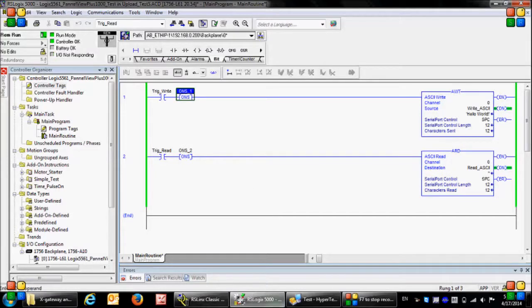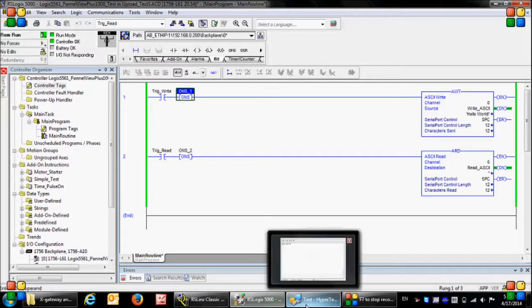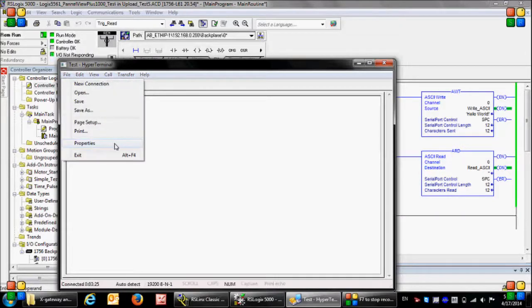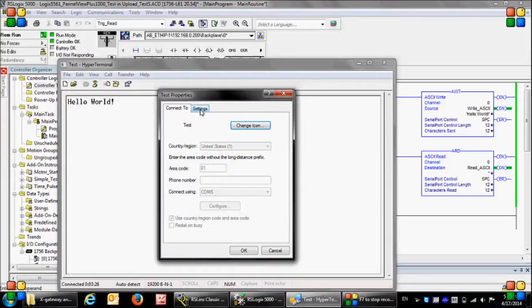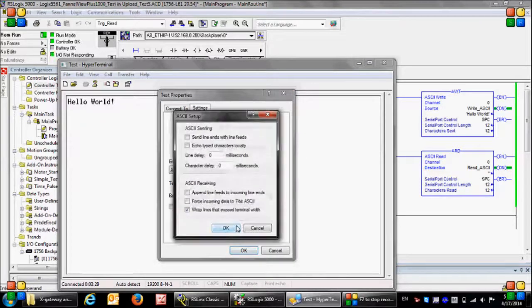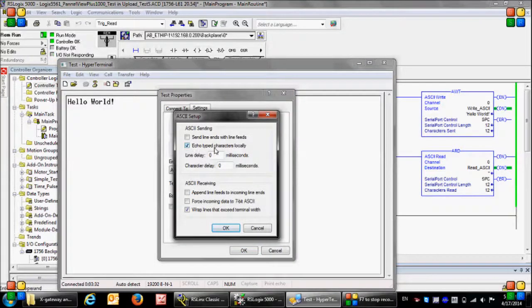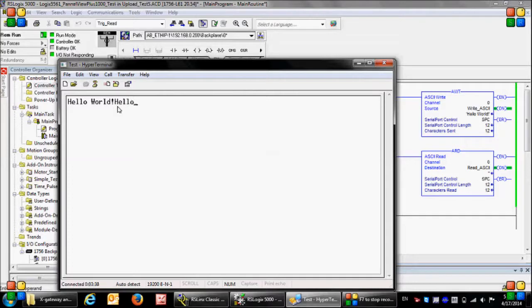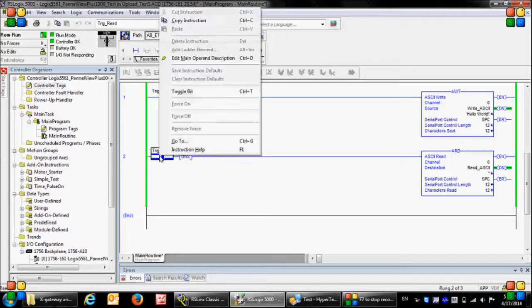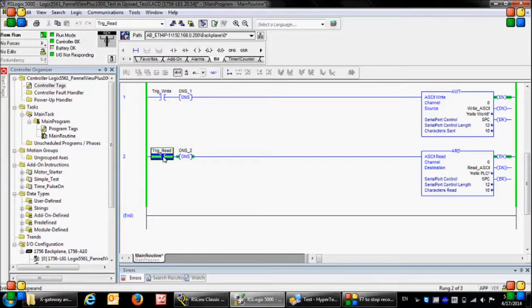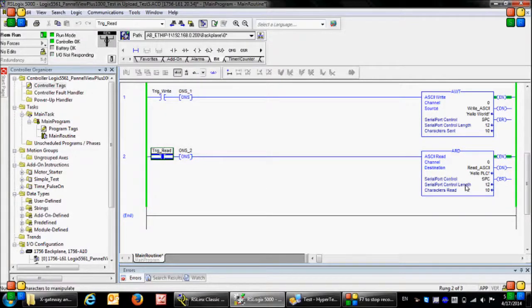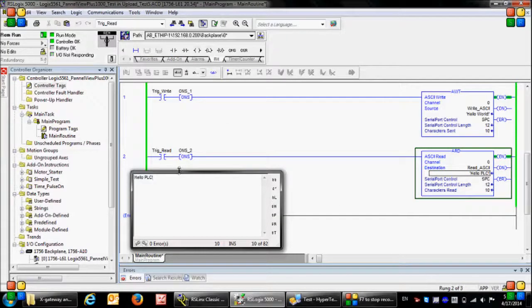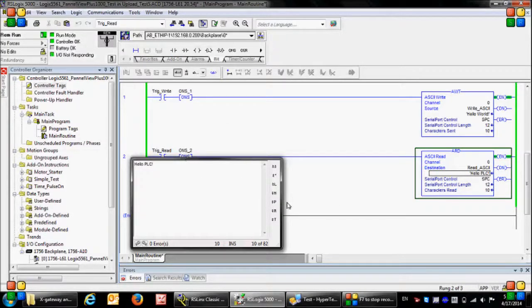Now I'm going to the HyperTerminal to send a message to the PLC. Here let's first go to the properties settings, ASCII setup, and enable the echo type the characters locally so that we can see what we are writing. Hello PLC, hello PLC is my desired message. Now here I'm going to activate the trig read bit and let me check the read. There you go, we have got the message from HyperTerminal.